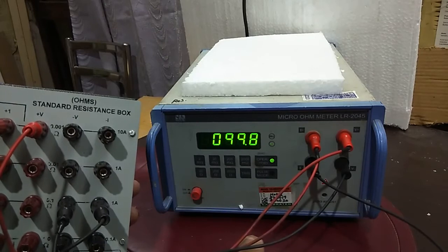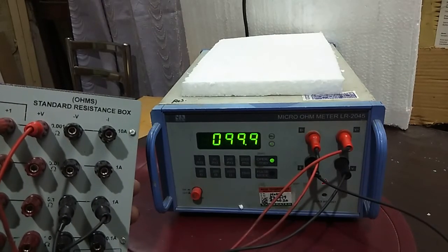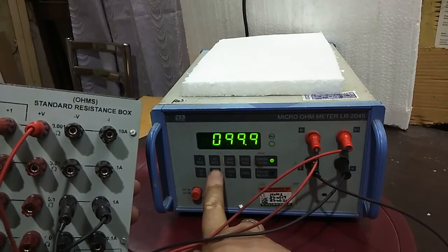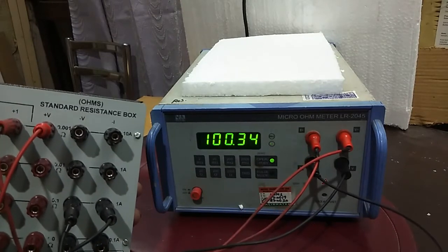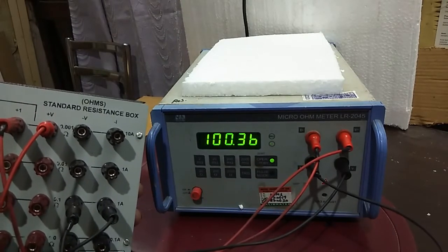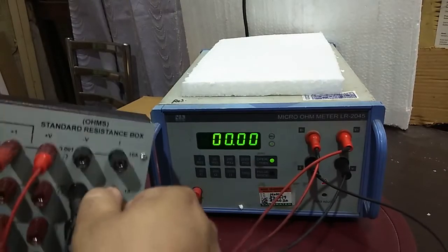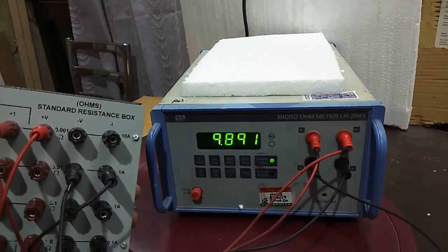I'm now putting it one hundred ohm. This is a hundred ohm, it is showing ninety nine point nine ohm. This is two hundred ohm. The instrument is working fine, working in all the ranges.